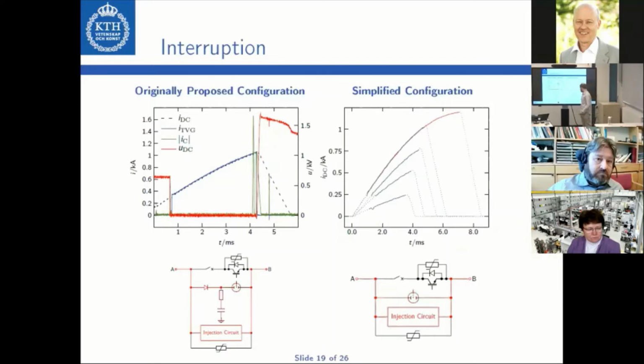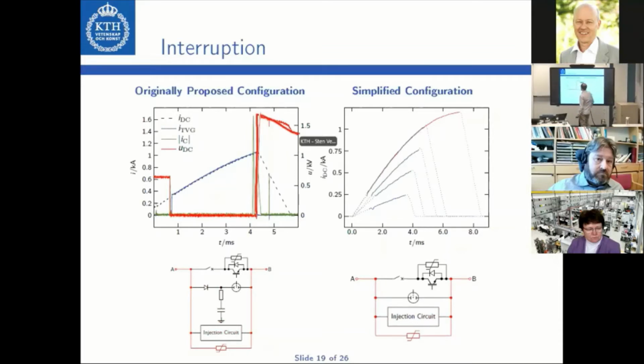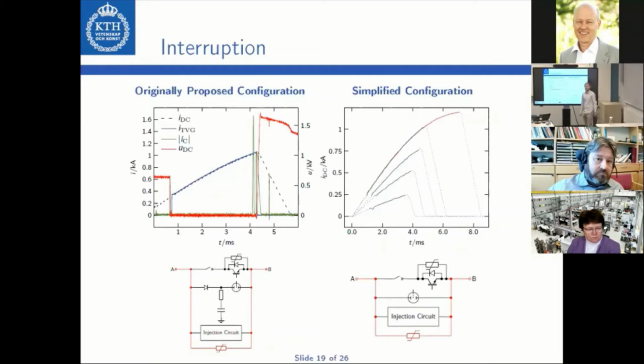In the next state, the fault current recharges the RC circuit and the energy storage of the injection circuit. The injection circuit voltage starts to increase. At some point, it is so high that the voltage also on the MOV causes it to become conductive because of its nonlinear properties. This is the counter voltage that is inserted by the MOV in this state, which then also interrupts the current flow. We have tested this process from low currents up to high currents of 1.2 kiloamp, as illustrated here for the simplified configuration. And we have not observed any limitation in the interruption process for the tested current levels.